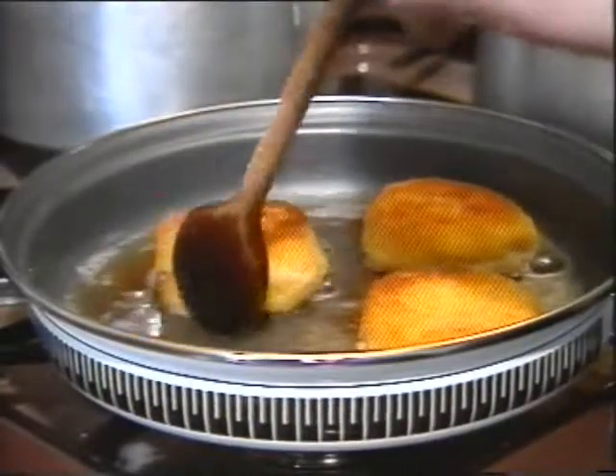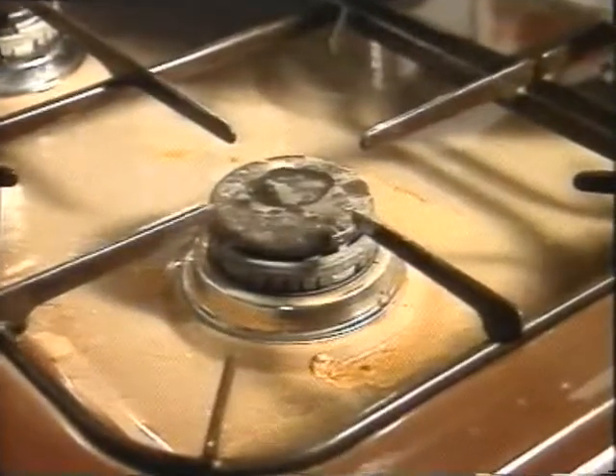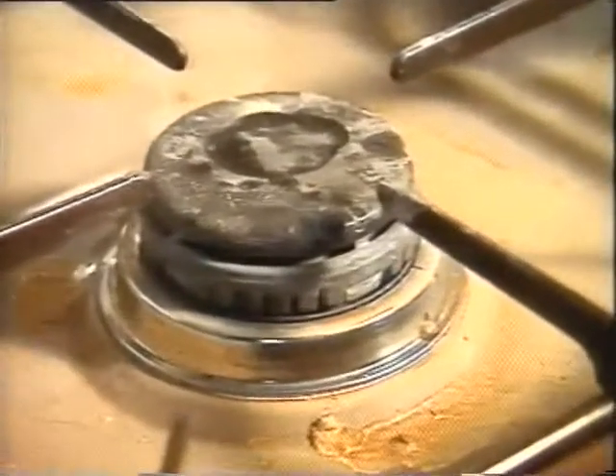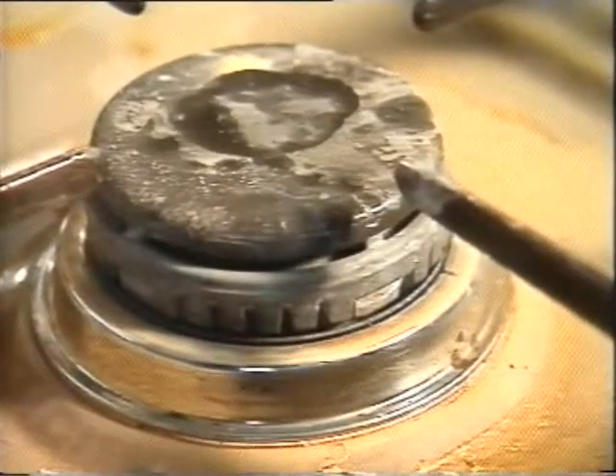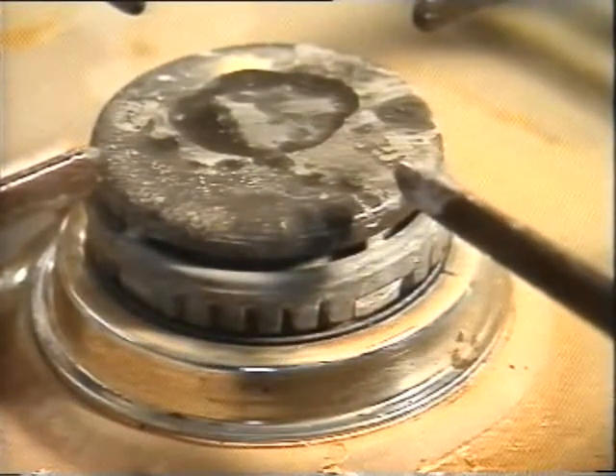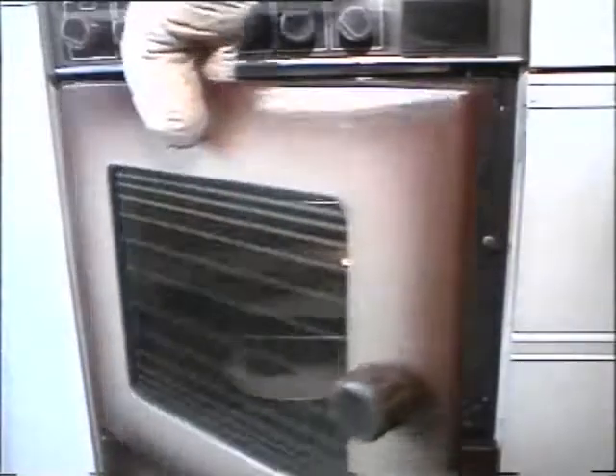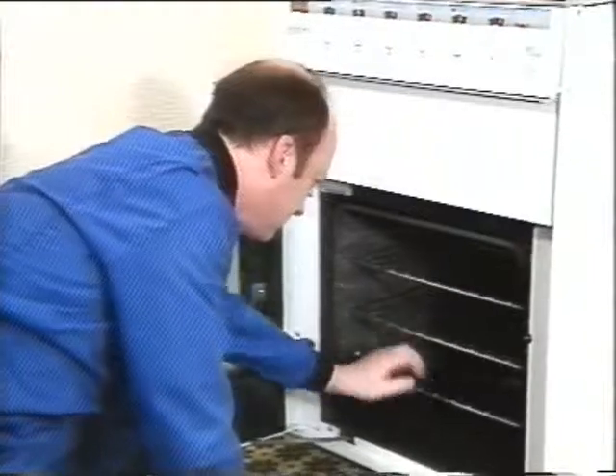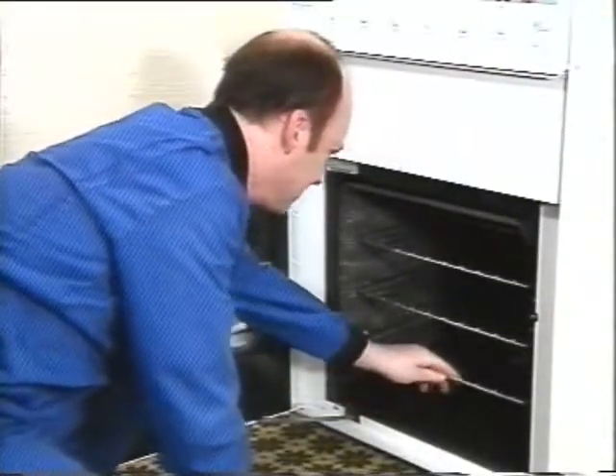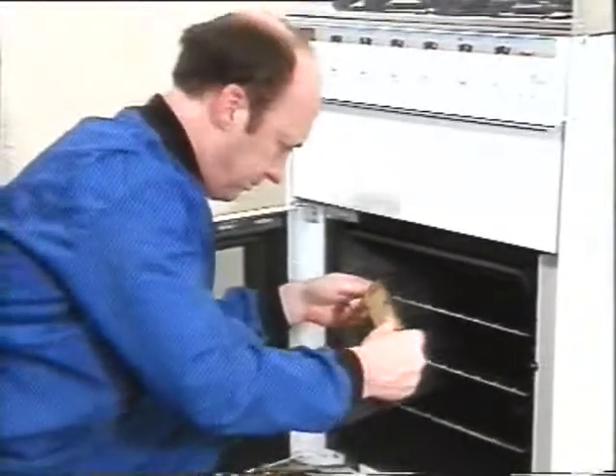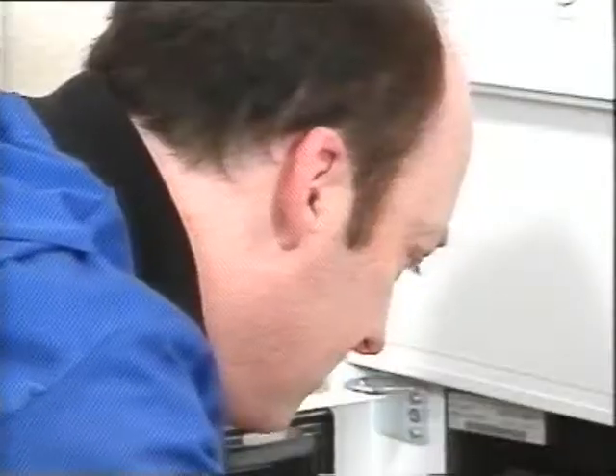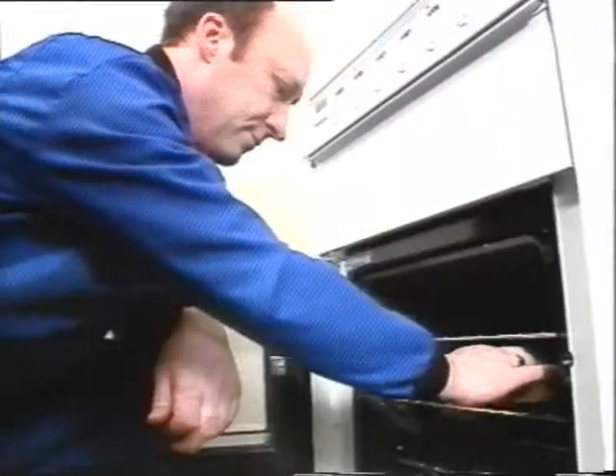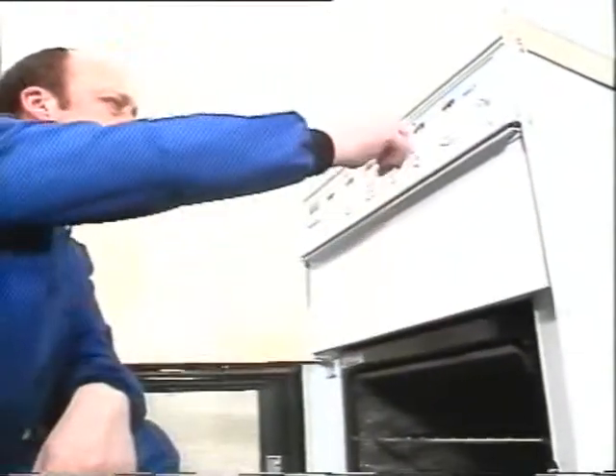Some of the faults that can occur are caused by spillages and other everyday results of cooking. They can cause blockages which may lead to ignition problems, poor combustion, unstable flames and smells. The cure is to give the cooker a good clean. If the customer is finding that food is being cooked unevenly in the oven, there are several possible causes. The cooker may not be level, the linings could be misplaced or the shelves distorted. If it's not any of these things, do a systematic check on the cooker's features, flame picture, gas pressure, ventilation, and so on.